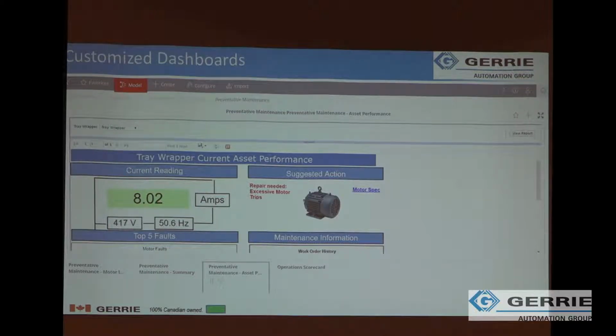So for preventative maintenance, this is a huge benefit for people because right now people are just, maybe they have a chart: every 6 months, go and check the bearings on this machine, every 3 months maybe go change a shear or a blade or something on a line. This lets you take a look at that data, report it, and develop real predictive maintenance, not suggestions. You could look at the machine, and instead of changing out a shear every 6 months, maybe it needs to be changed every 3 weeks. You've been producing sub-quality product for those 5 months until you've made that change.